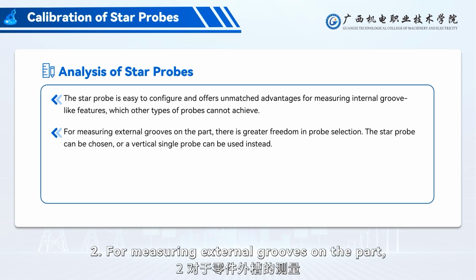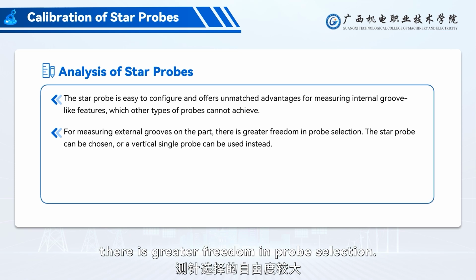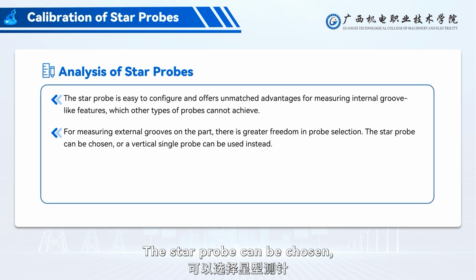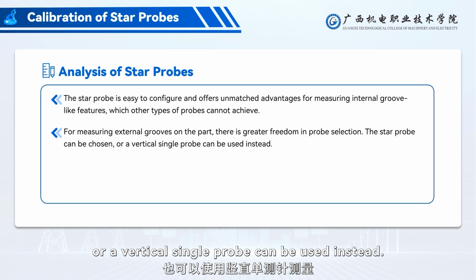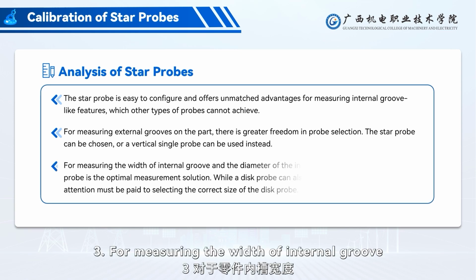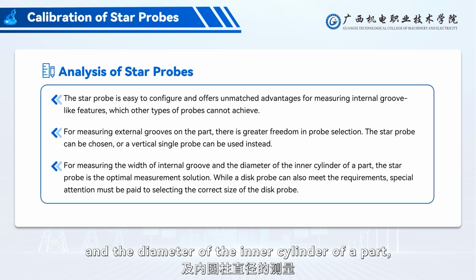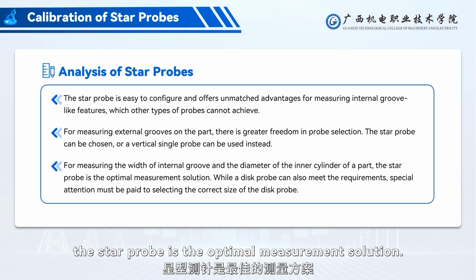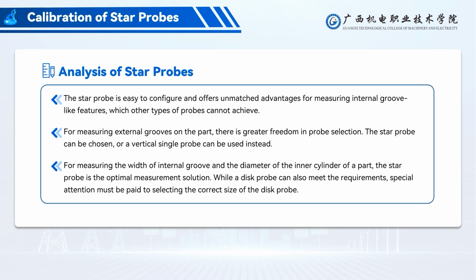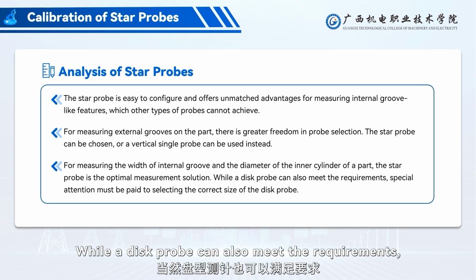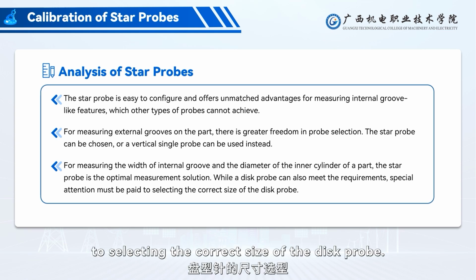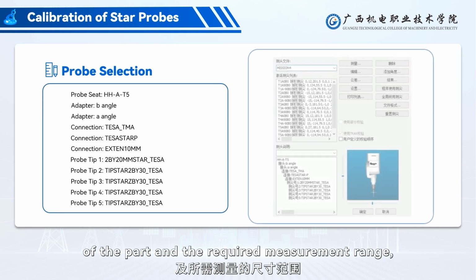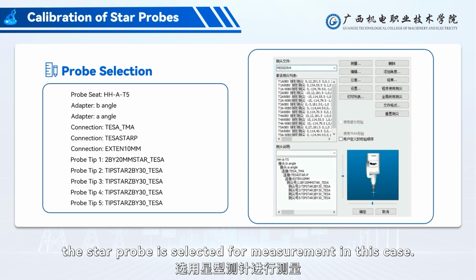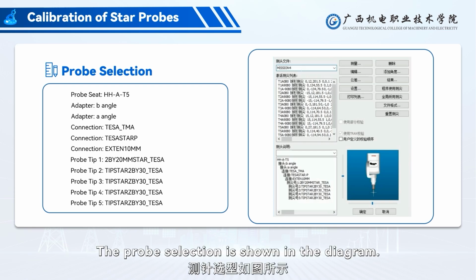2. For measuring external grooves on the part, there is greater freedom in probe selection. The star probe can be chosen, or a vertical single probe can be used instead. 3. For measuring the width of internal groove and the diameter of the inner cylinder of a part, the star probe is the optimal measurement solution. While a disc probe can also meet the requirements, special attention must be paid to selecting the correct size of the disc probe. Therefore, based on the feature distribution of the part and the required measurement range, the star probe is selected for measurement in this case. The probe selection is shown in the diagram.